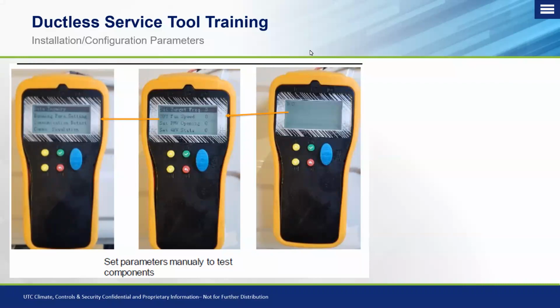Okay, so when you plug in and get your screen all powered up, you use your up and down arrows on there to go to the running parameter setting menu and make sure that it's highlighted. You hit the green button to select that and get into that running parameter setting menu. And then from here, inside this menu, you'll see a setting target frequency, fan speed, PMV opening, a 4-way valve state. In order to change something, so if we were to change the target frequency on here, we'd want to go ahead and hit the green arrow to get into that. And you'll see from here, it's at 0.0.